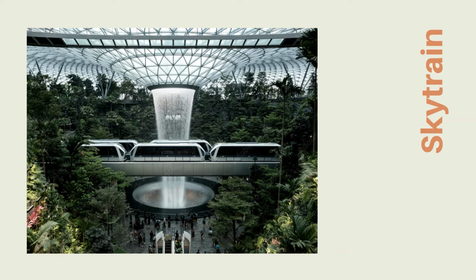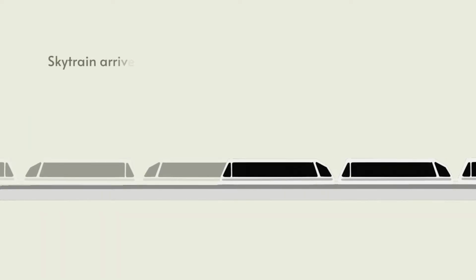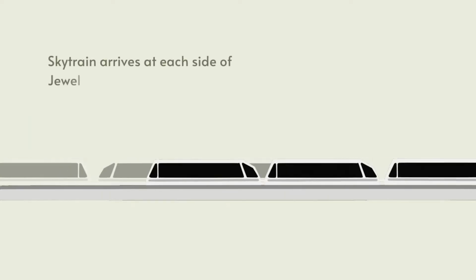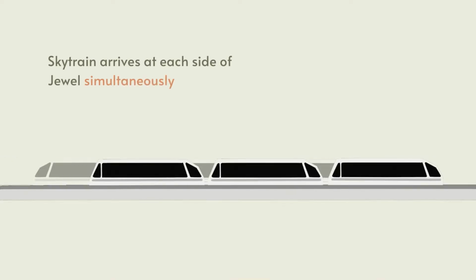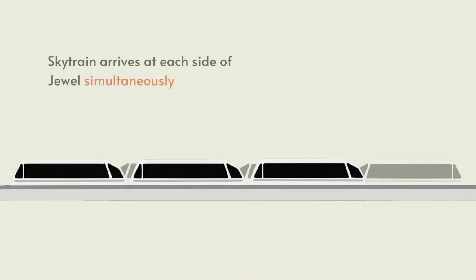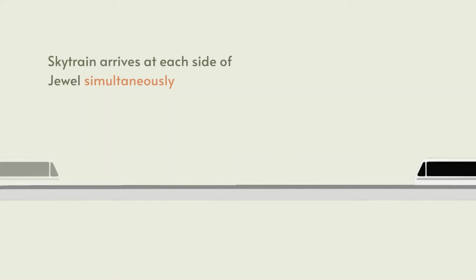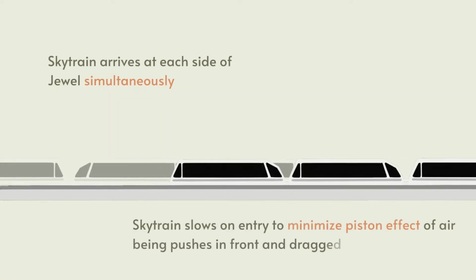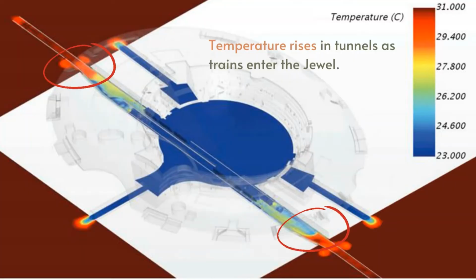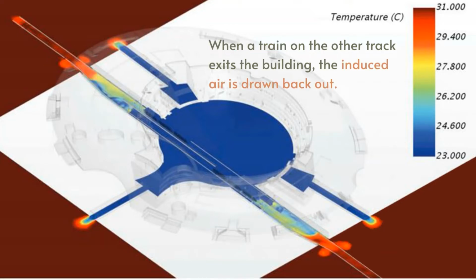The SkyTrain. The SkyTrain plays a significant role in controlling hot air within the dome. Both trains arrive simultaneously and slow down upon entry to minimize the piston effect of air being pushed in front and dragged out from behind. The temperature rises at the tunnel openings of the SkyTrain. Doors at the entrance and exit of the tunnel open and close rapidly to prevent hot air from entering the dome. When the train on the other track exits the building, the induced air is drawn back out.